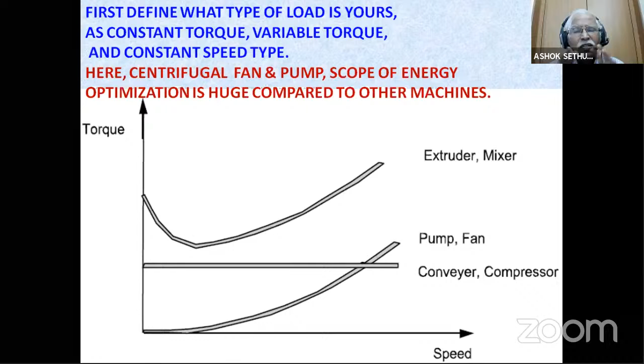There are three types of loads: variable torque loads, constant torque loads like a conveyor or a compressor, and on the reciprocating side, positive displacement compressors. These are all constant torque. Whereas a screw centrifugal compressor or a screw compressor are variable torque, and blowers and centrifugal pumps and centrifugal blowers are all variable torque machines, variable torque systems. If you analyze the systems of constant torque, variable torque, and constant power, then you know how much energy conservation is possible in each and every system.